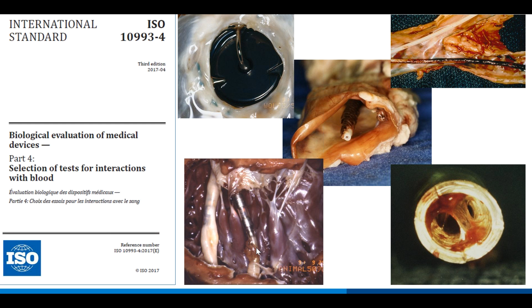So the main place that people open to in this particular standard is this table 1, which shows the test categories. It's divided by hemolysis and thrombosis areas, and thrombosis itself can be divided into in vitro and in vivo tests.